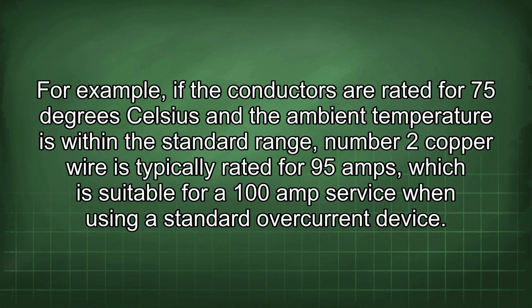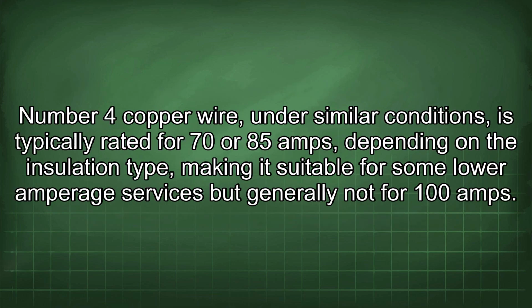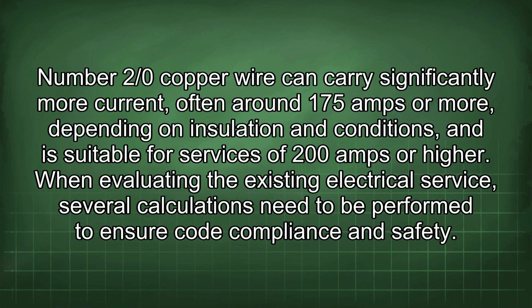For example, if the conductors are rated for 75 degrees Celsius and the ambient temperature is within the standard range, number 2 copper wire is typically rated for 95 amps, which is suitable for a 100 amp service when using a standard overcurrent device. Number 4 copper wire, under similar conditions, is typically rated for 70 or 85 amps, depending on the insulation type, making it suitable for some lower amperage services but generally not for 100 amps. Number 2/0 copper wire can carry significantly more current, often around 175 amps or more, depending on insulation and conditions, and is suitable for services of 200 amps or higher.